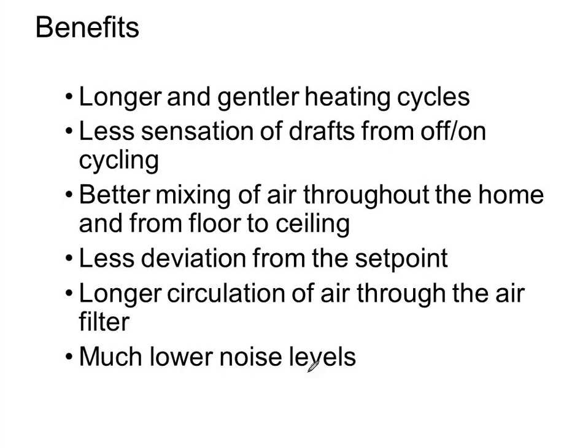Instead of having to hit high fire and then off, high fire and off, which has a lot of noise associated with it, we're always going to be somewhere in the middle range. We almost never will be at high fire unless it is actually 0 degrees outside. There's only a couple times that this guy's going to run at 100% capacity. One is if it's a design day, right? 0, -4 degrees, -5 degrees, whatever. Okay, fine. Then it runs full capacity.